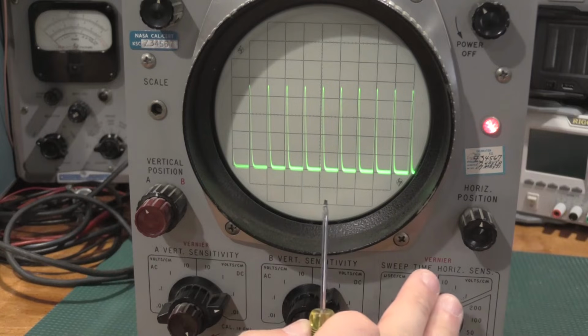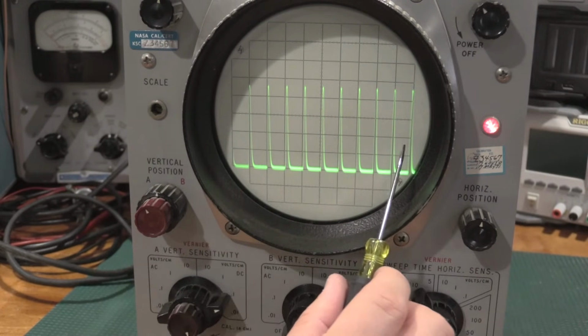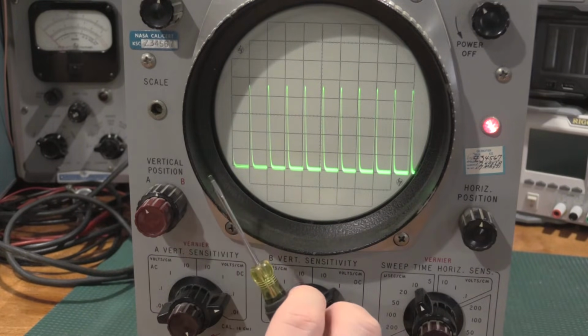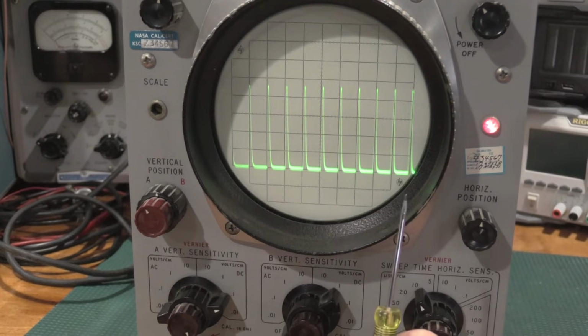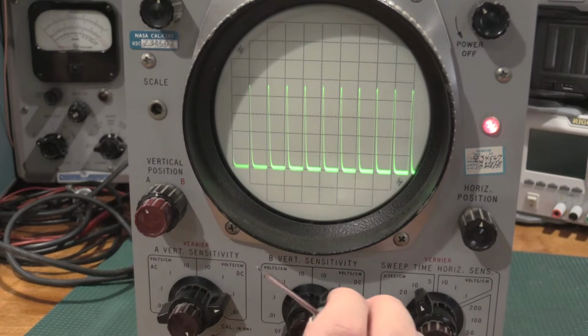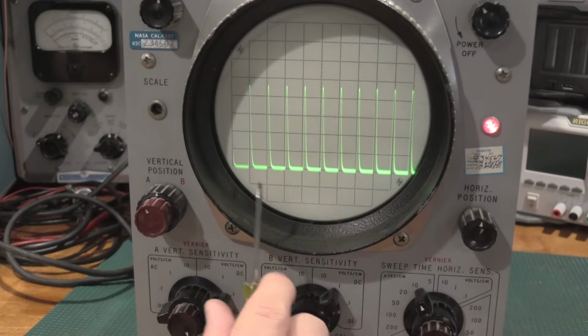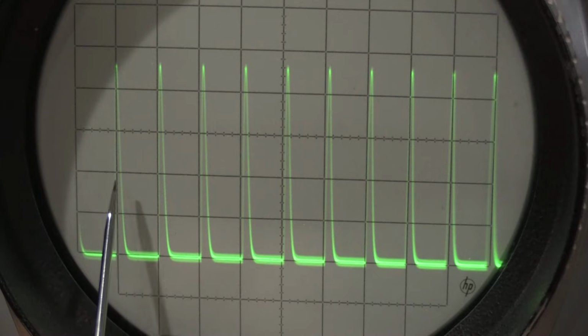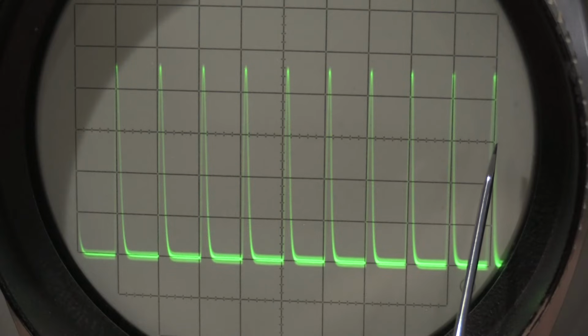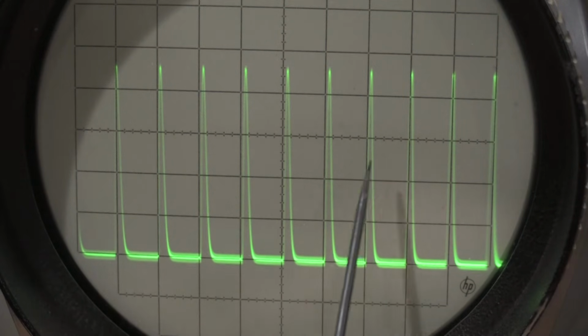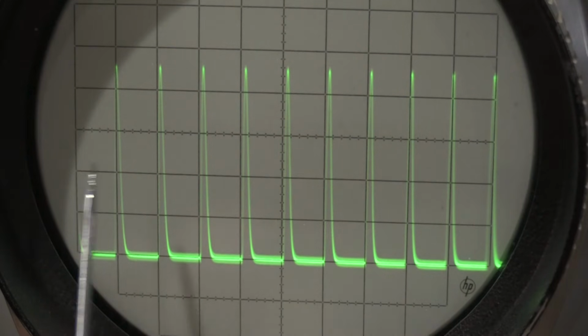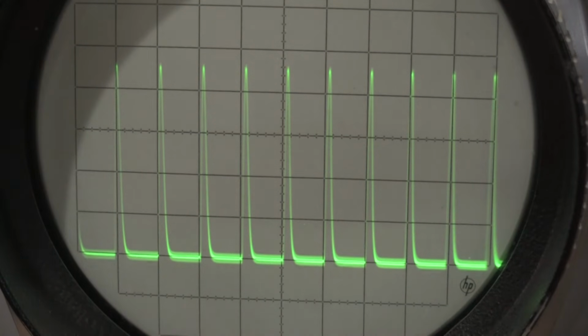The timing, unadjusted: I hit 10 time marks between 9.5 and 10.5 centimeters, and my actual sweep time is 2.5% fast for the scope on the 10 microsecond testing. The interesting thing is, if we look really, really close, we have a good time mark here lined up with the graticule, and a good time mark over here lined up with the graticule. But in the center, we have a little bit of deviation throughout this range. So while the full sweep is relatively consistent and 2.5% fast, it's speeding up and slowing down. It's not linear. So the sawtooth that's driving the horizontal isn't a linear ramp. I understand that I am nitpicking a scope that was made in 1960, but it's just an observation from what the time mark generator is telling me.